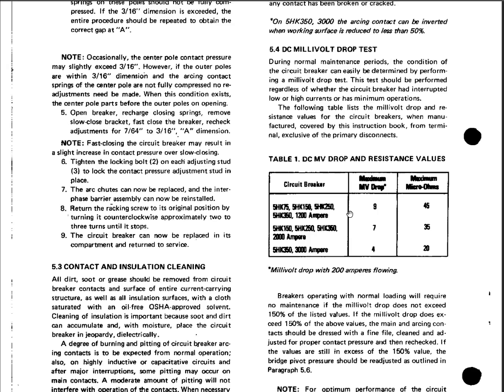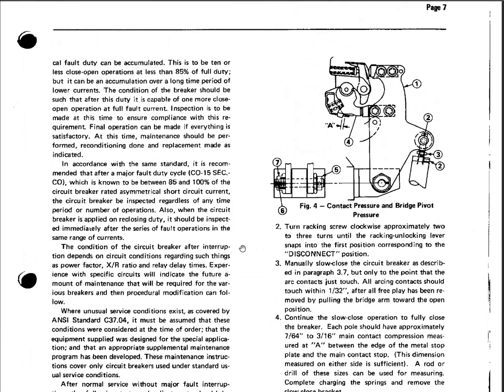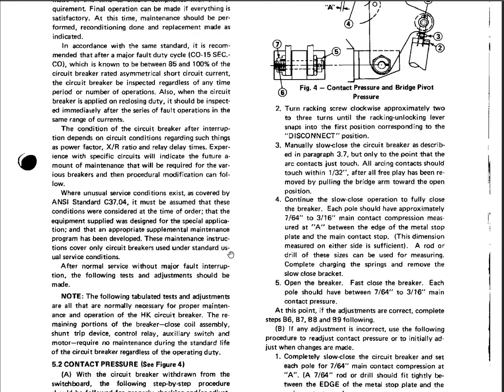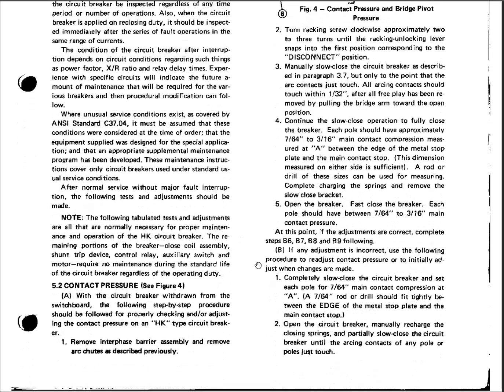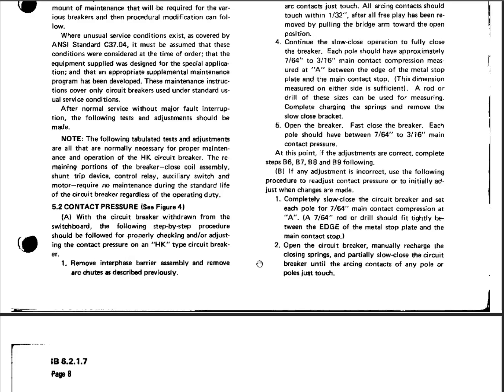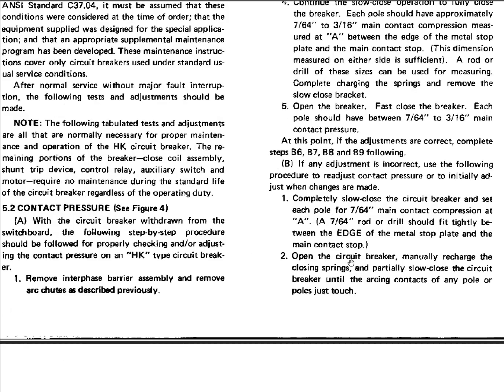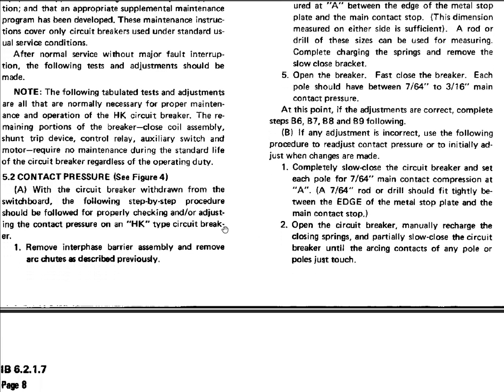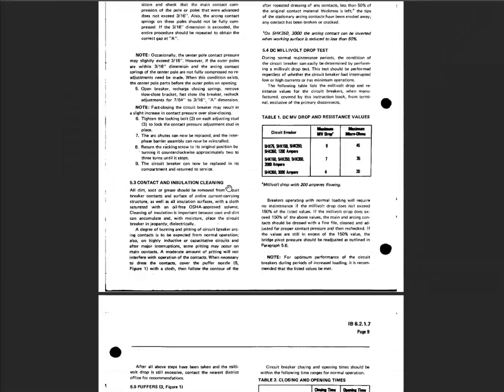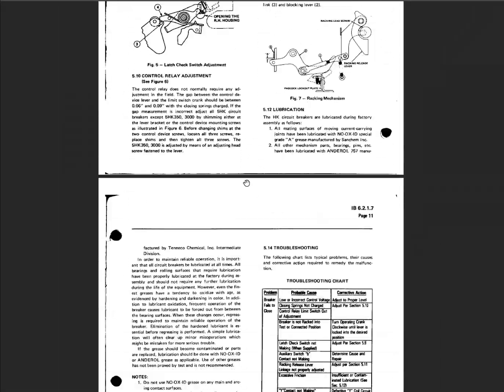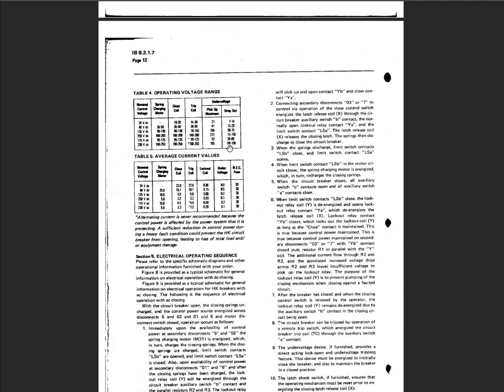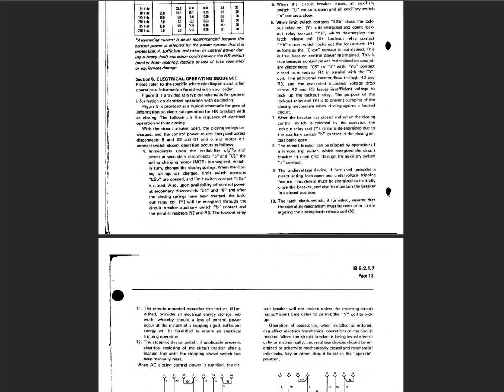So there's that one. There's a lot of mechanical checks, and they start on page 7 in this manual. Everything from gap distances, contacts open, pressures of contacts closed. I mean, you've got a lot of stuff that you're supposed to check here. Main contact compression is listed right here. There's a lot of things to check, and they go in and out of every single page all the way down towards the end of this book. So there's a lot of stuff to check here, and all of them should be checked.